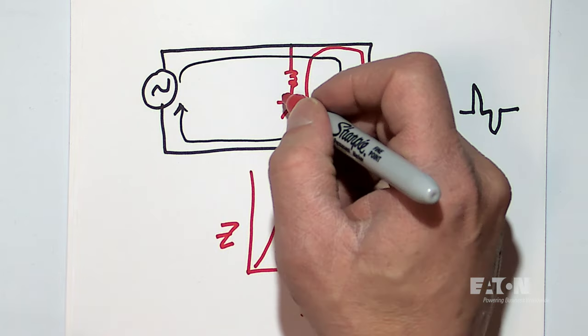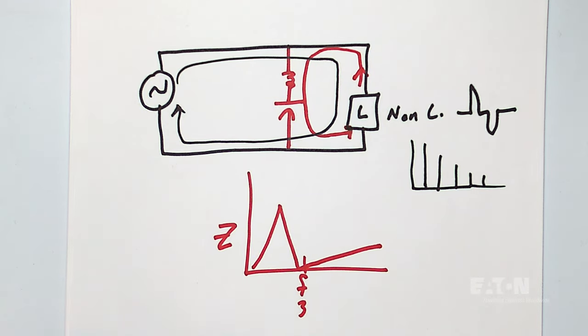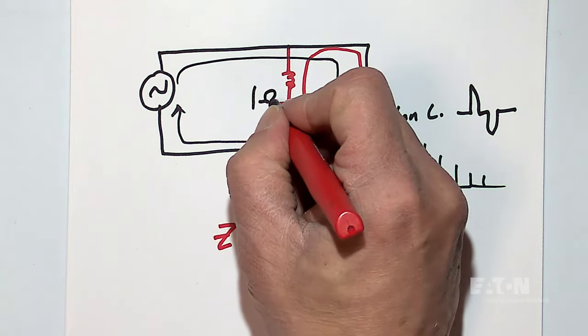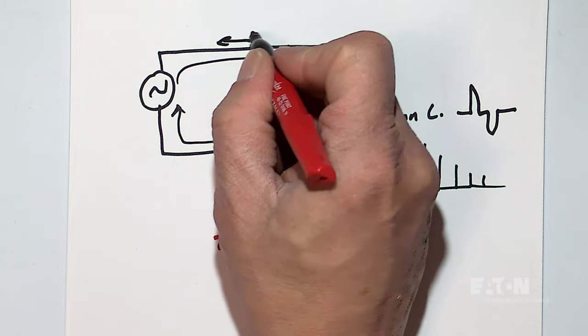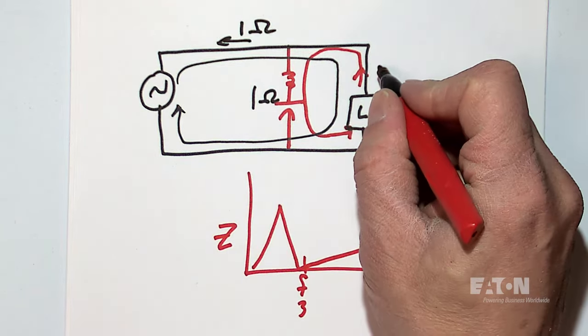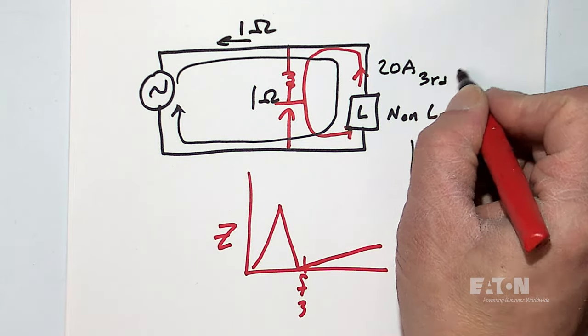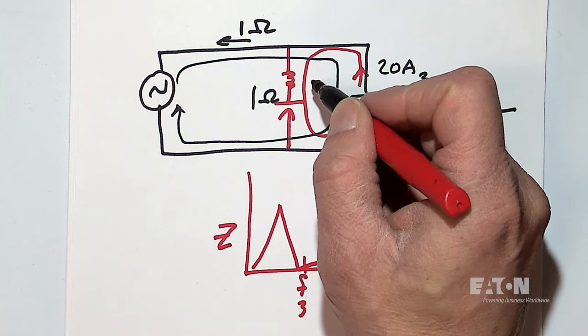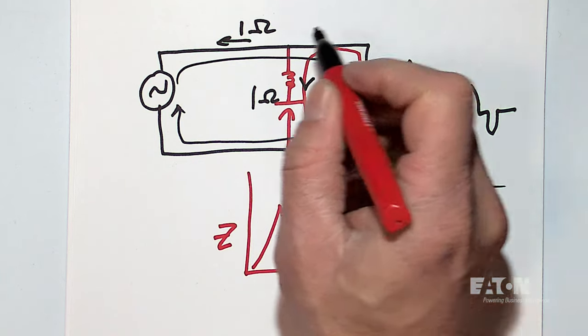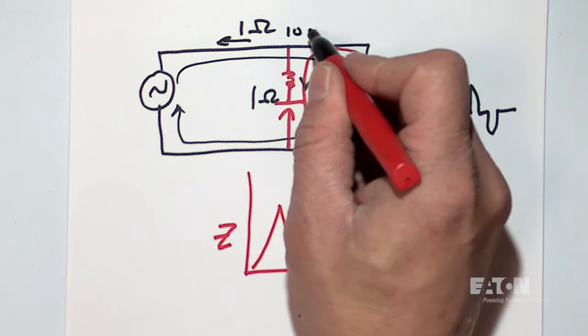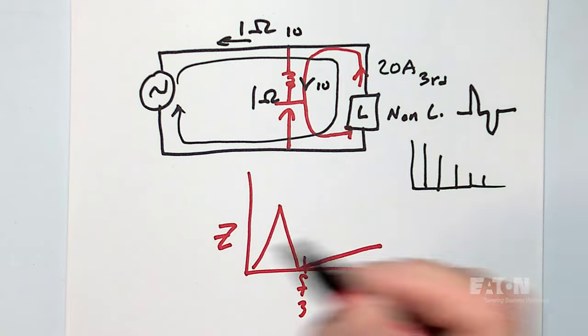Let's say the impedance of this path is one ohm, and let's say the impedance of this path is one ohm. And if I put out, let's say, 20 amps of third harmonic current, I'm going to have, and we've talked about this in other videos, 10 amps going here and 10 amps going here. That's how current divides.